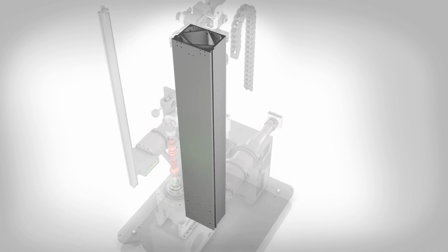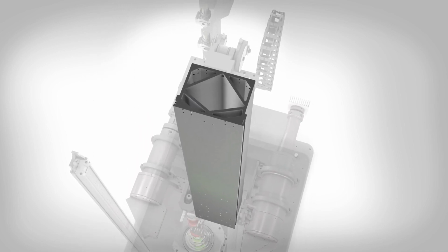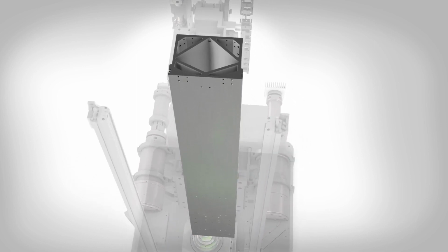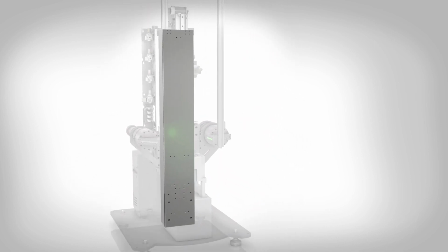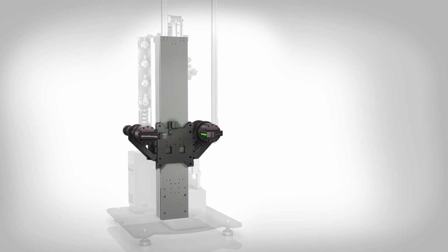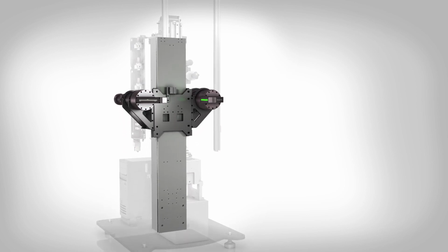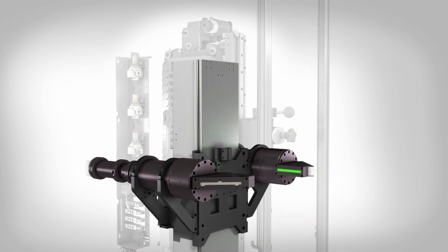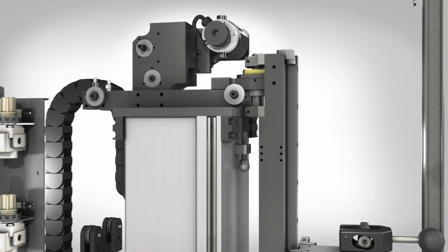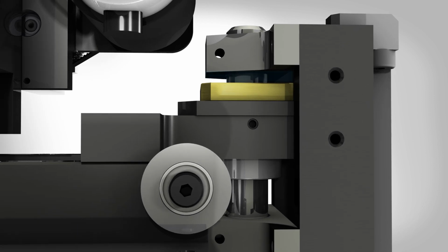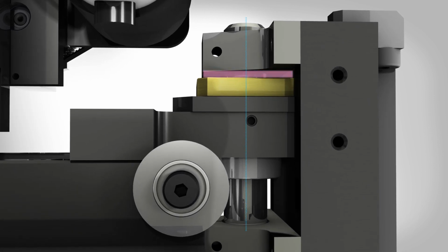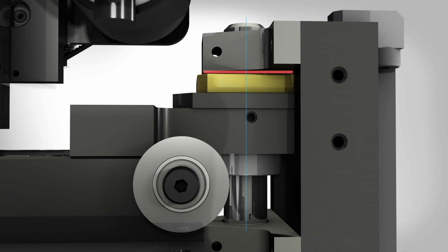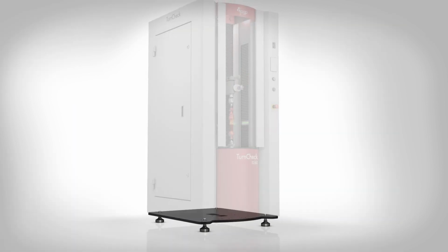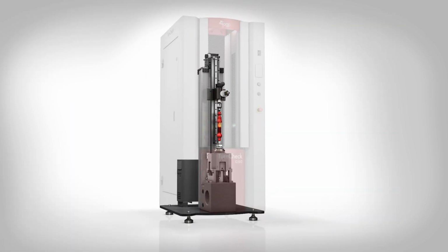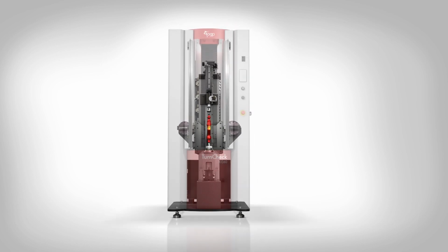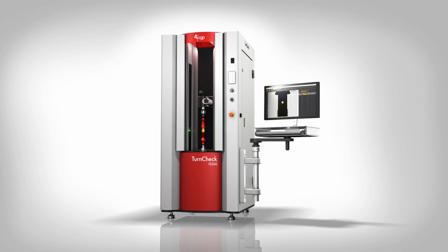An extruded aluminum column with an internal lattice provides highly rigid support for the optical motion assembly. A patented bearing weight design isolates the optical motion from the effects of thermal expansion. The tailstock beam is constrained radially, but remains compliant in the linear axis, decoupling the thermal expansion of the aluminum support column from the steel tailstock. Each carefully selected material is monitored and compensated to maintain thermal stability and long-term repeatability.